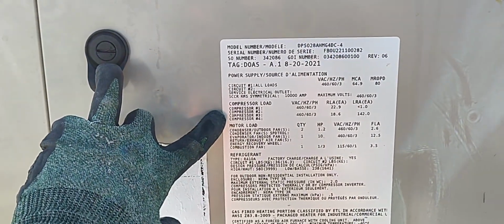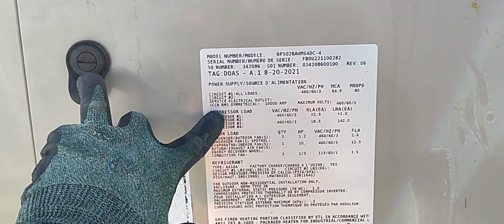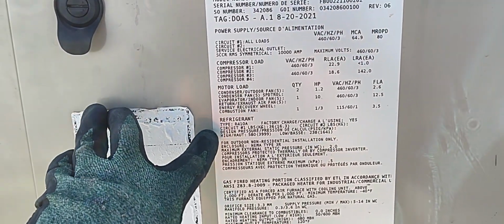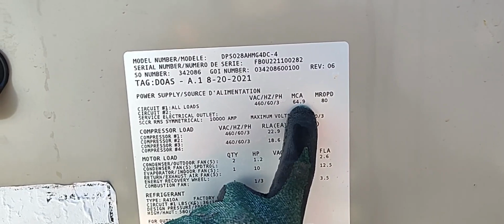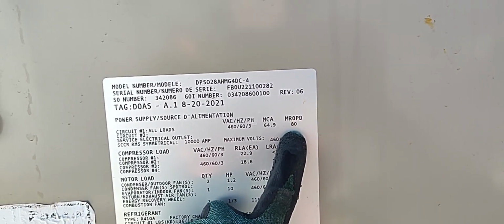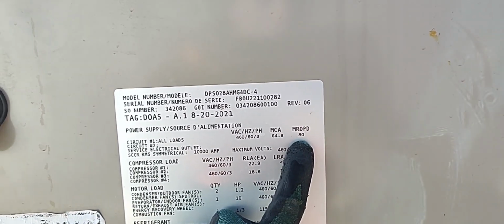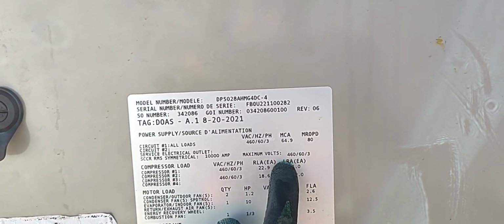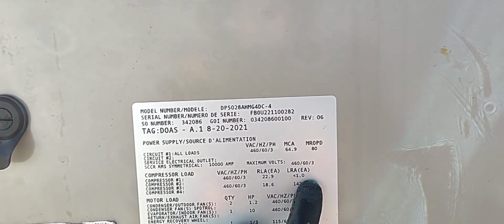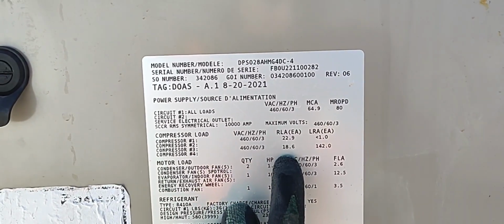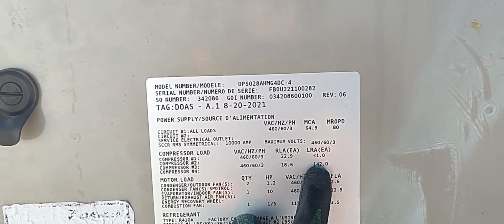So if we come right here, on this nameplate on the outside, we have compressor load, motor load, refrigerant, the power supplies, max circuit ampacity, max rated overcurrent protection device, maximum volts 460, RLA each, LRA each. So let's open this guy up.